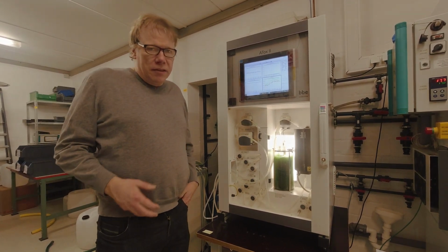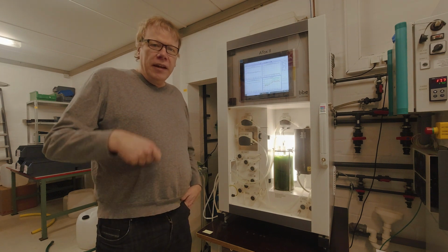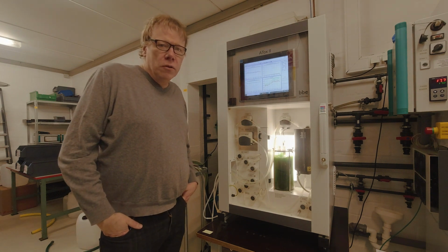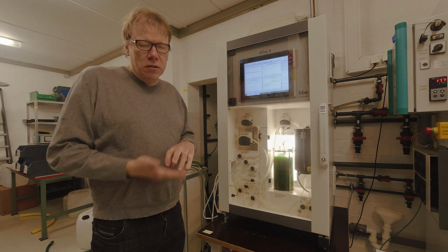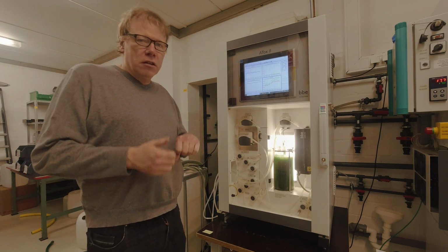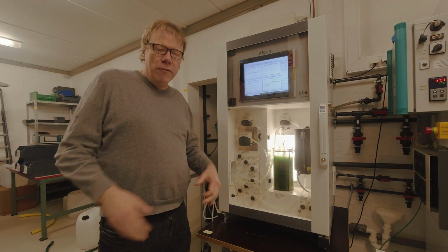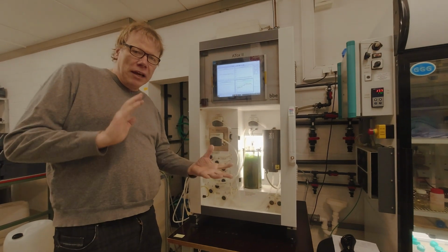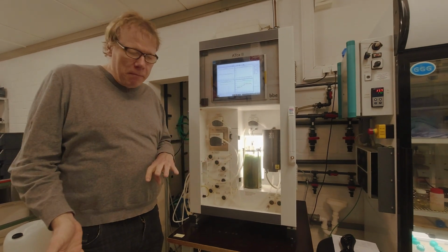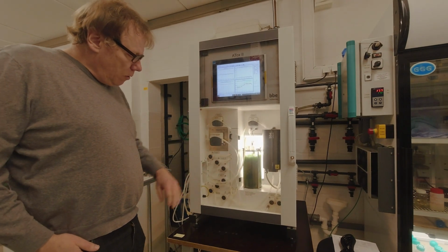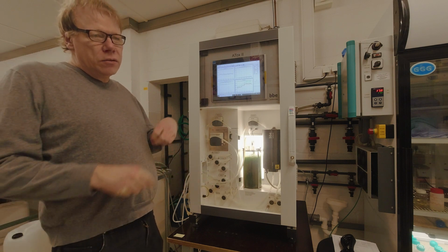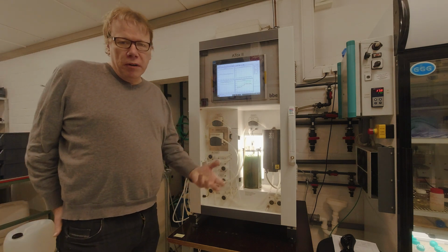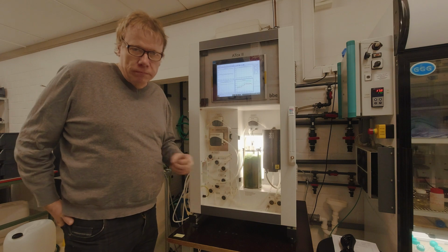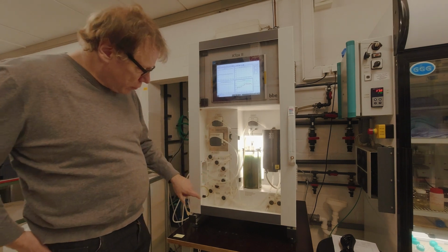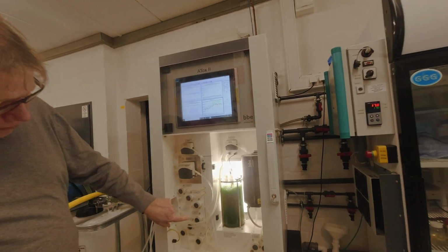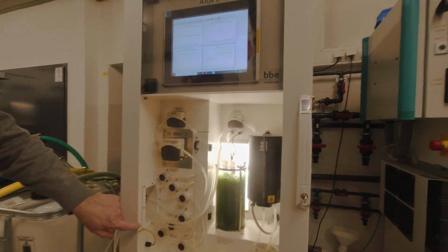From time to time, let's say 1 time a day or 2 times a day, you test the sensitivity of the instrument. The algae culture should always be of the same quality, but in reality it may vary over time. So with the reference toxin, you see the response to a defined toxin of a defined concentration. So these are the 3 valves for the selection of the input water.